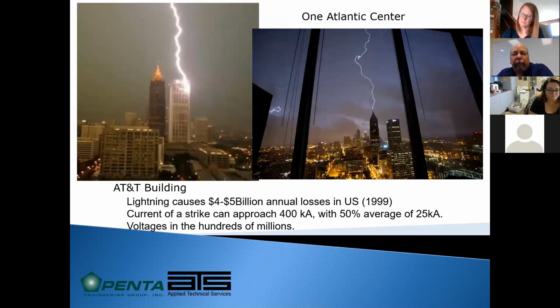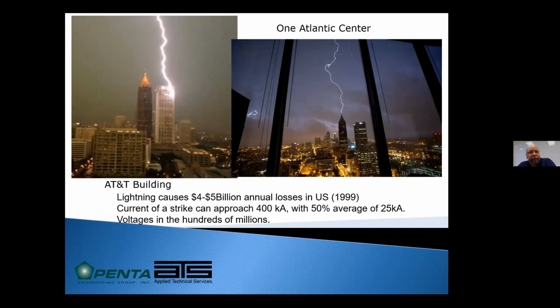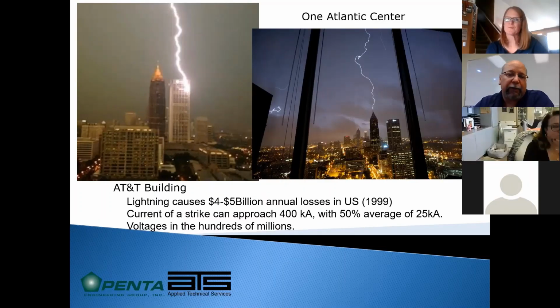But lightning can do an extreme amount of damage, not only to people, but also to buildings and property. These are a couple of buildings in the Atlanta area that have been struck. Lightning causes an estimated $4 to $5 billion in annual losses, from 1999 data. The current of a strike can approach 400 kiloamps, and on average about 50% of strikes are at least 25 kiloamps. The NFPA, National Fire Protection Association, has a standard, NFPA 780, that we use in this country for design of lightning protection systems. And Underwriters Laboratories, UL, has UL 96A. The two standards basically mirror each other with very slight differences, but those are our design standards that we follow here.